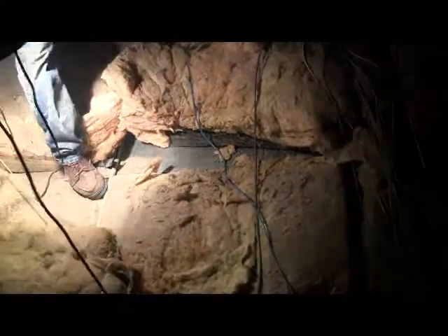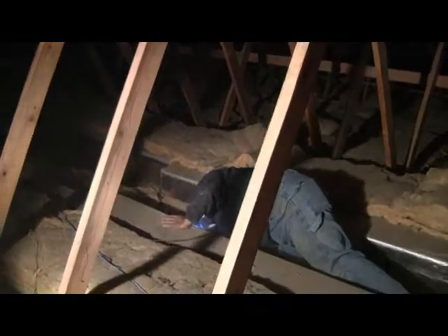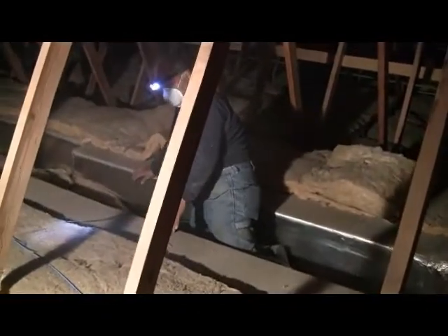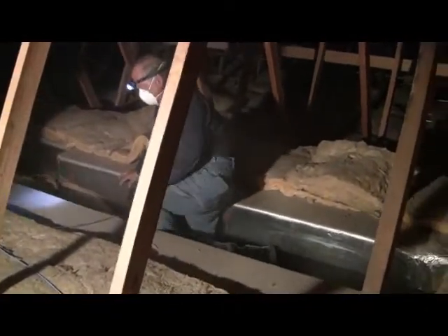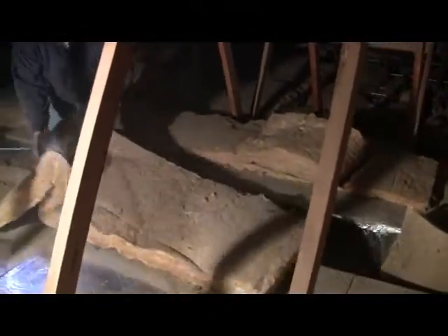And I'm also getting back here on the back side, and I'm looking down behind this duct, and just by pushing this down, I'm seeing a big puff of smoke coming out. There is a metal boot, but its joint between itself, the metal boot, and this return is not sealed. And this is not something that's necessarily a flaw of the installation. It may just be over time.